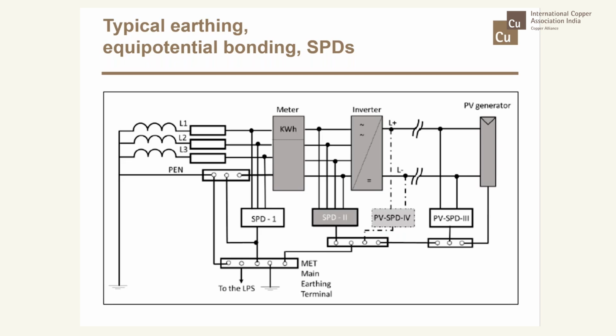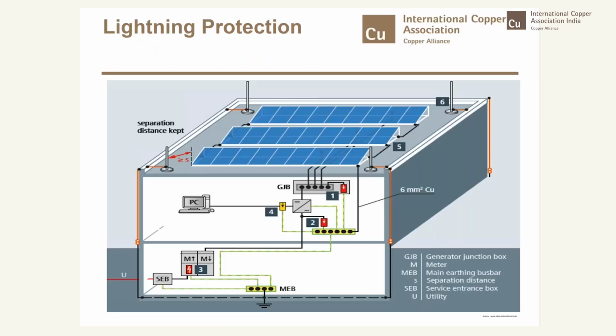In fact, if you look at the interconnecting side, it is surge protection 1, which is the toughest in that class. So all types of categories are appearing in this rooftop. This particular requirement is under amendment in the upcoming NEC subdivision.